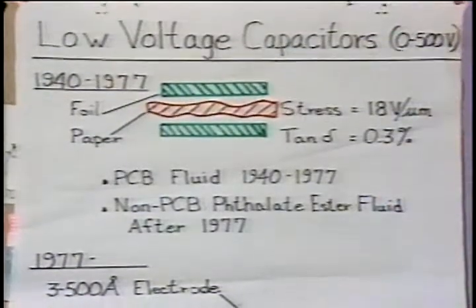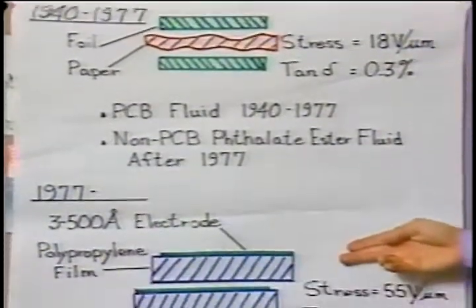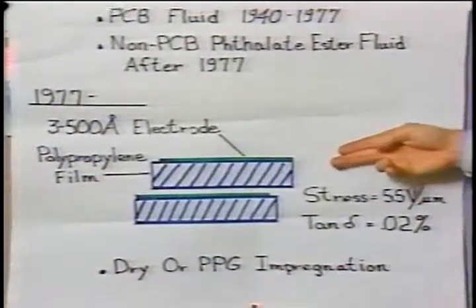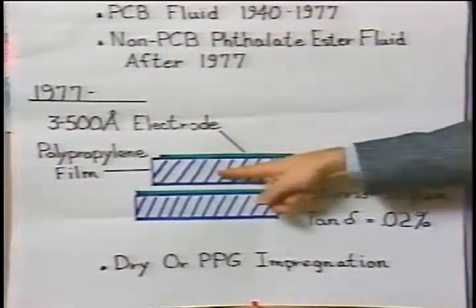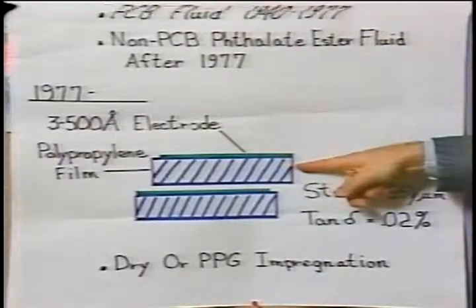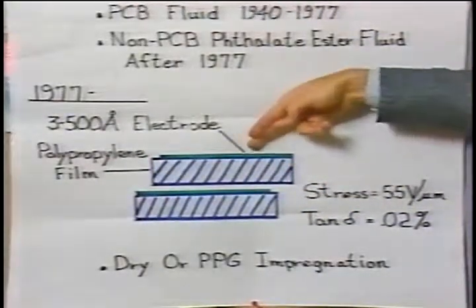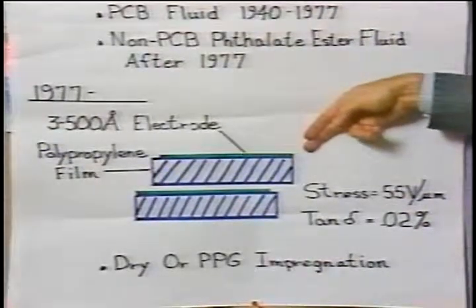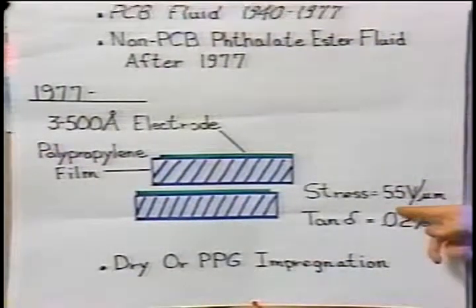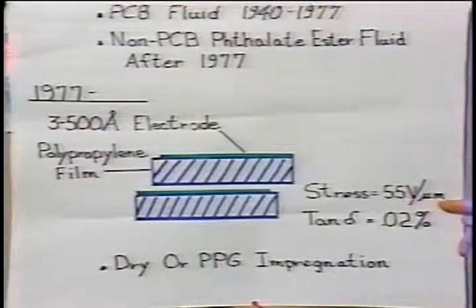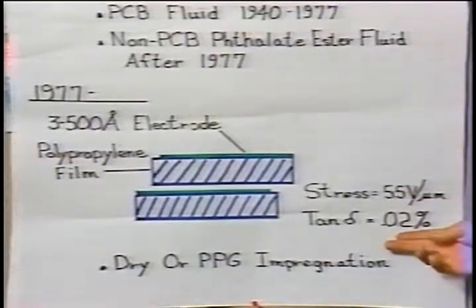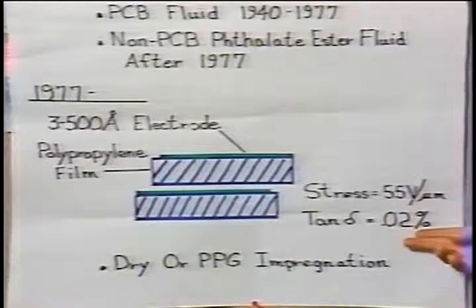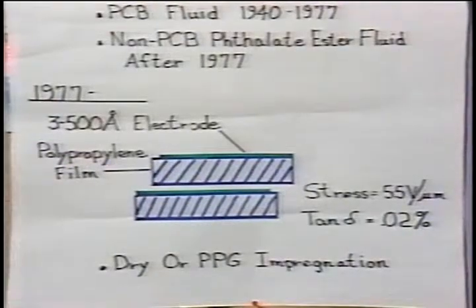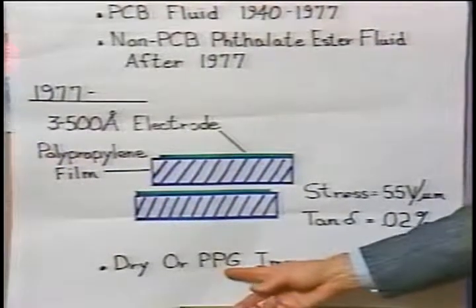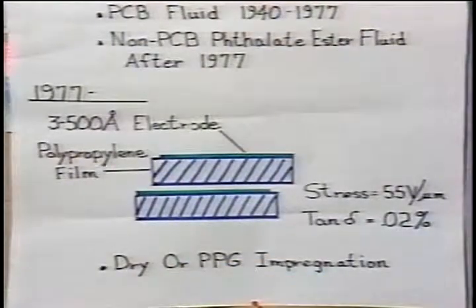In 1977, a revolutionary change took place in low voltage capacitors. Metallized polypropylene film was introduced as a dielectric. The electrodes were 300 to 500 angstroms of aluminum. The stress, as you can see, took a dramatic jump to 55 volts per micron, and the dissipation factor plummeted to 0.2%. This capacitor could either be made impregnated with a fluid like polypropylene glycol or in a dry form.